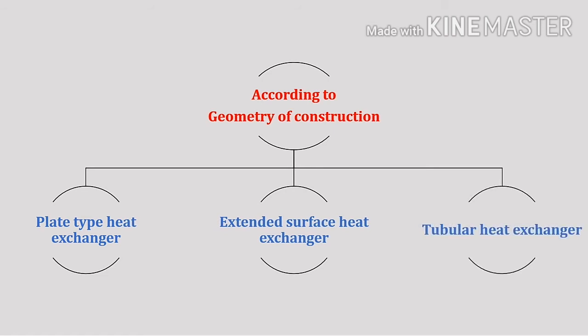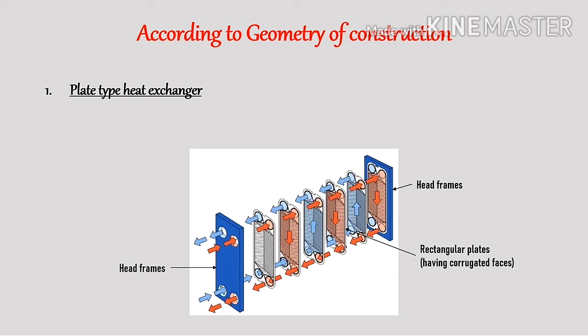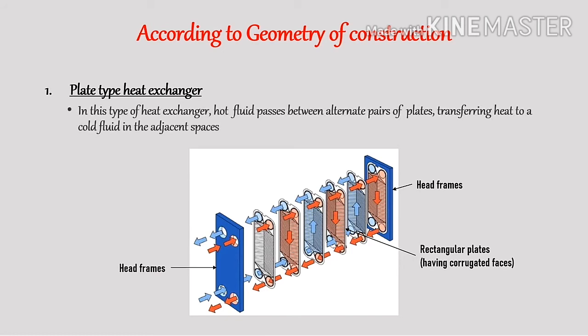According to the geometry of construction, the first type is the plate type heat exchanger. A plate type heat exchanger consists of a series of rectangular parallel plates held firmly together between head frames. The plates have corrugated faces, which provide a high degree of turbulence even at low flow rates. It is provided with inlet and outlet nozzles for fluids at the end. Hot fluid passes between alternate pairs of plates, transferring heat to the cold fluid in the adjacent space. Plate type heat exchanger is very compact, requires a very small flow space, can be easily dismantled and cleaned, and provides a large heat transfer area in a small volume.